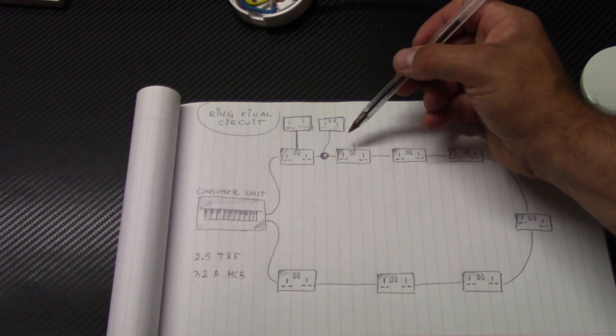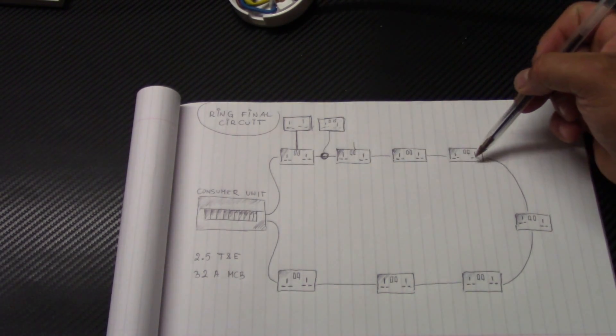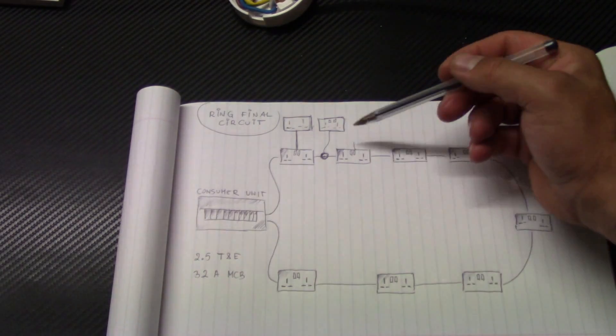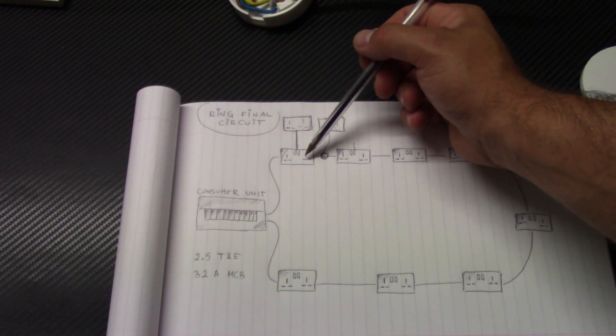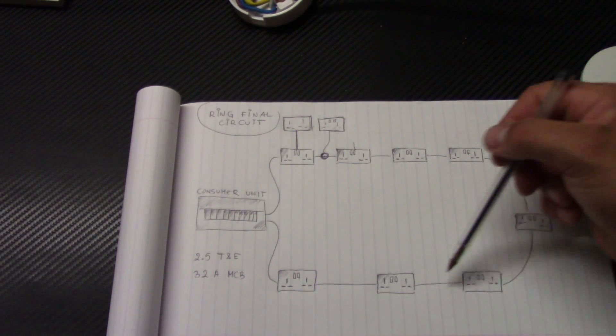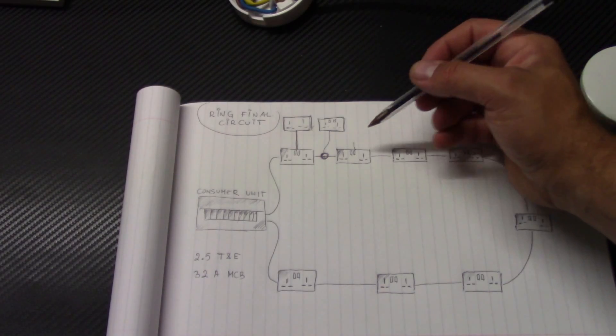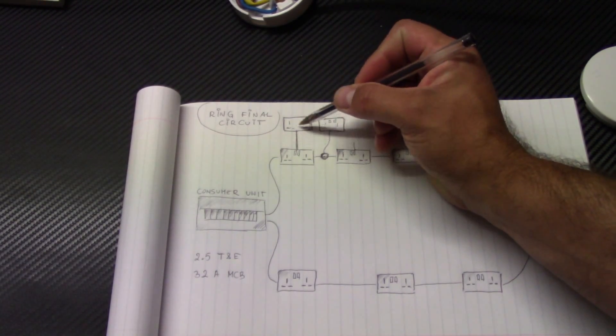They are limited by the number of sockets that you've got on the ring. For example, if you've got in this ring eight sockets, the unfused spurs you can have only eight.